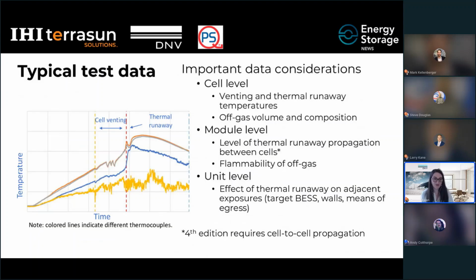Before we move on, I do want to stop for a moment and talk about what thermal runaway actually is. Thermal runaway is ultimately the uncontrollable self-heating of a battery. A cell undergoing thermal runaway will have chemical reactions that produce heat that then in turn cause chemical reactions that produce heat, which causes this cycle of self-propagation. Typical test data for a cell undergoing thermal runaway usually looks something like what is shown here. There are 2 important temperatures during any thermal runaway reaction, the cell venting temperature and the thermal runaway onset temperature. These temperatures are described with those dashed lines that you see. It is possible to cool the battery after the cell has vented, but before thermal runaway has been reached, to avoid thermal runaway, which is why these 2 temperatures are so important.